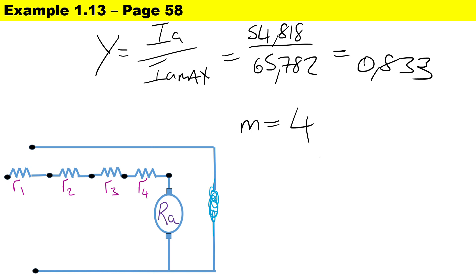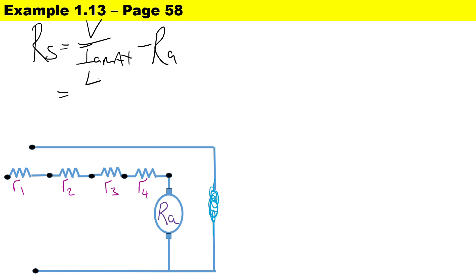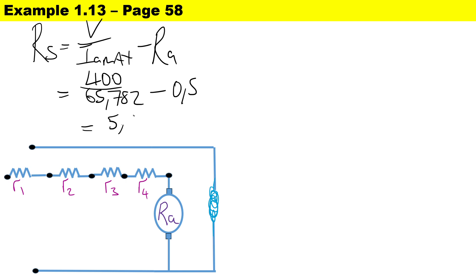Now that we have the ratio and the currents, we can calculate the total starting resistance. It is V over Ia_max minus Ra: the terminal voltage is 400 volts, the maximum armature current is 65.782, and the armature resistance is 0.5 ohms. The total starting resistance is 5.581 ohms.